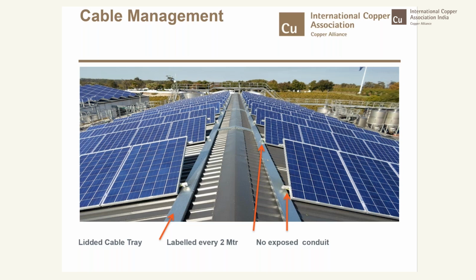You can see no exposed conduit here. Even the PVC conduits are not allowed. It has to be UV rated PVC conduits that we have to use beneath the panel. And conduits are not even visible, in fact. So that is a good cable management practice.